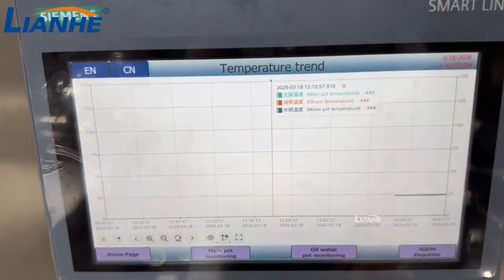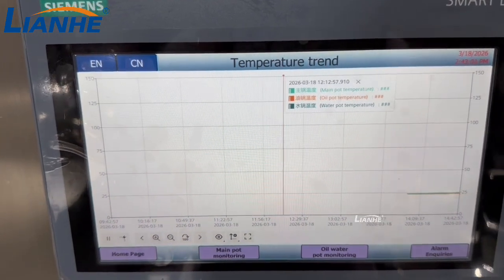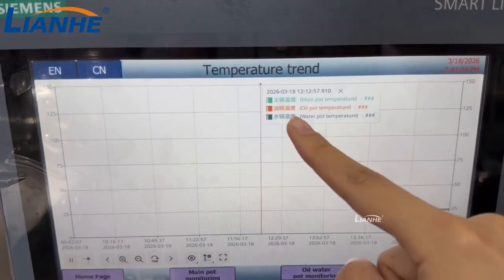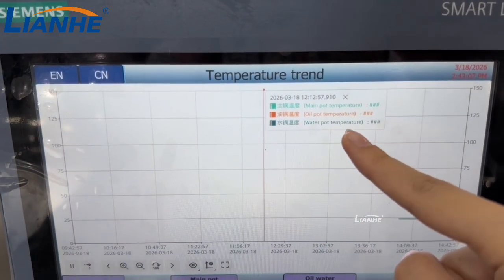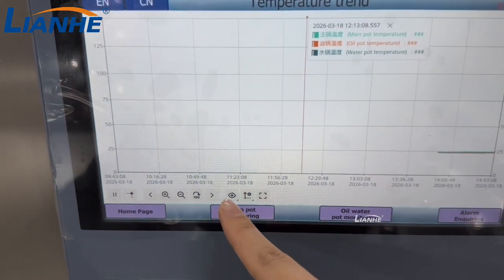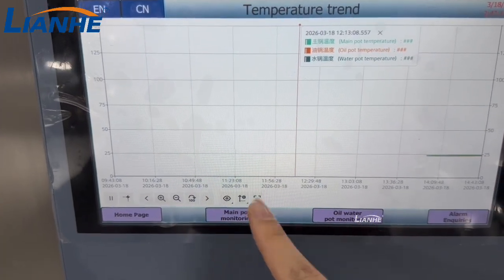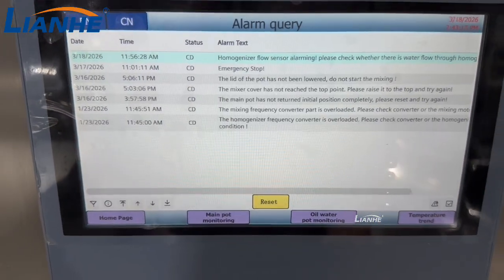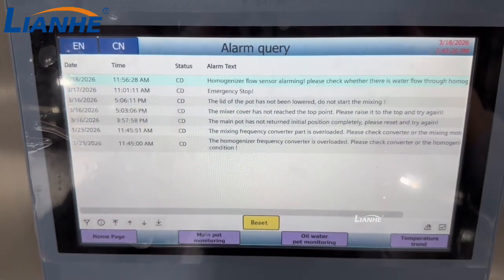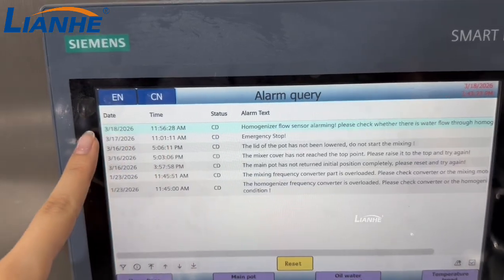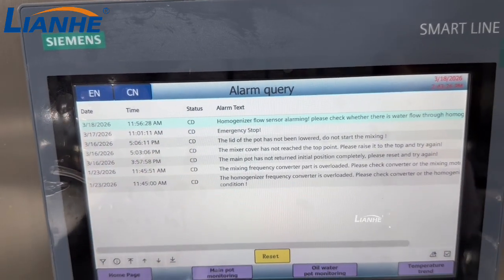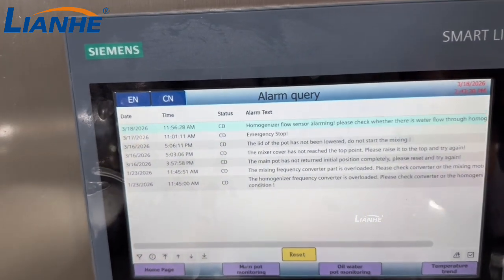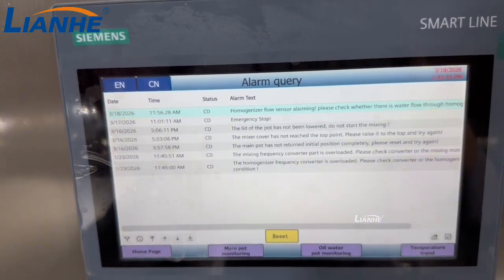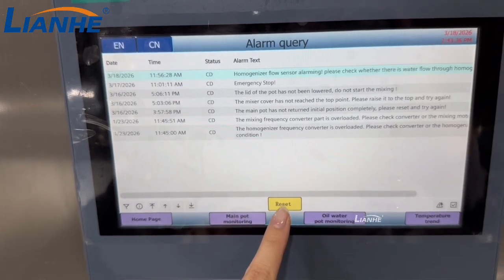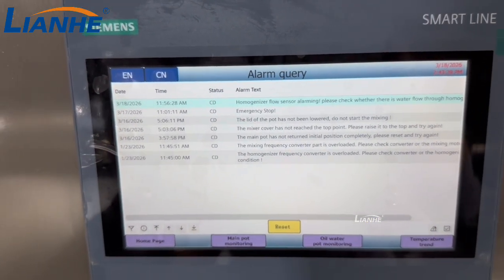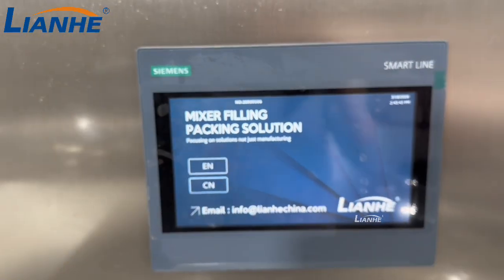Then let's check the temperature trend. You can check the temperature trend when you use the heating function. It will display different lines to show you the temperature here, and then you can use these buttons to check the temperature trend. And then this is the alarm inquiry. You can see the detailed alarm text from here. You can have the date, time, status, and alarm text to show you the problems of the machine, and then when you solve the problems, you can push this reset button to reset the alarm inquiries. Okay, and this goes back to the home page.